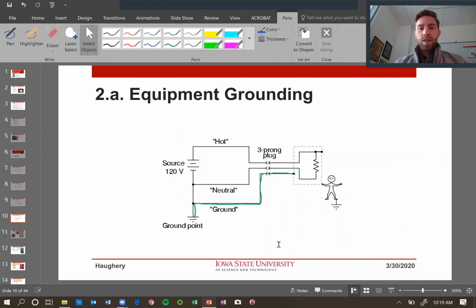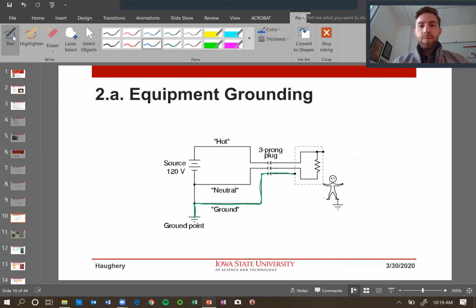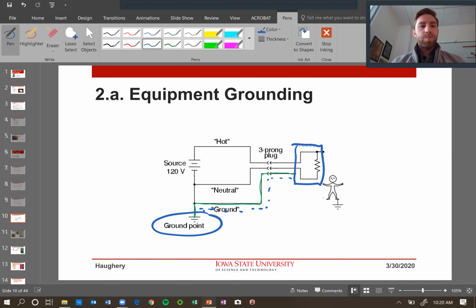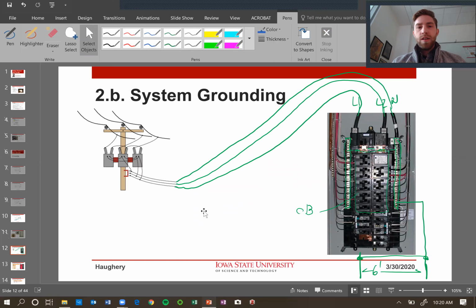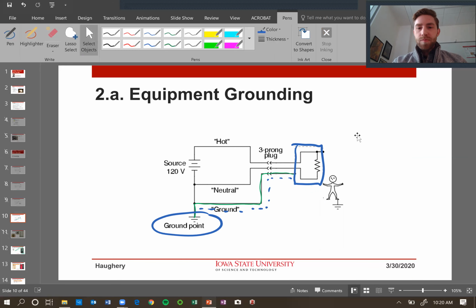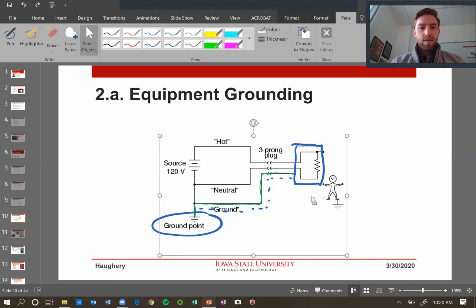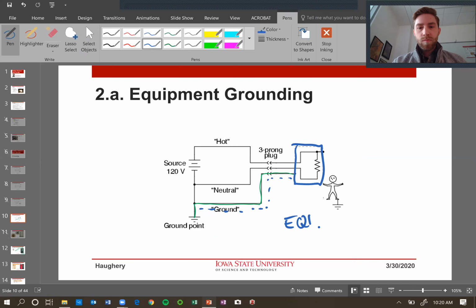So we're calling equipment grounding, really, that's when we have the piece of equipment, whether that's our drill or our box or our CNC machine that we have here, and we have a ground conductor connected all the way back to the grounding bar in the power distribution panel. And so that's a connection specifically from the chassis or the housing of the piece of equipment back to ground. And eventually that literally will go into the ground, into a ground bar. System grounding then is where we take the actual connection from the panel into the ground, okay? And so here is equipment. And then this point here is our system.